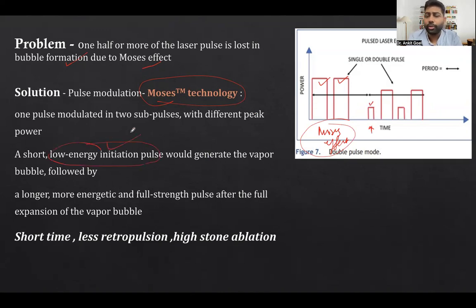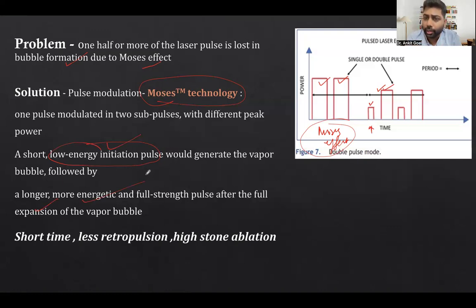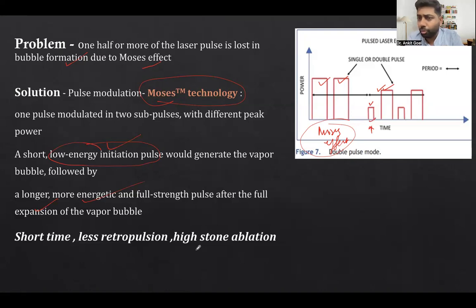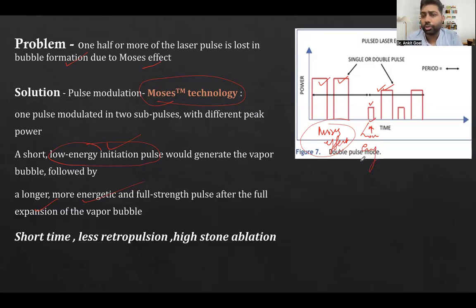The second high-energy pulse causes stone fragmentation through photothermal, photomechanical, and photochemical mechanisms, all acting more efficiently because the path has already been created by the low-energy first pulse. So: a small low-energy initiation pulse creates the path, then the high-energy pulse causes the actual fragmentation effect. This results in more stone pulverization and decreases operative time.